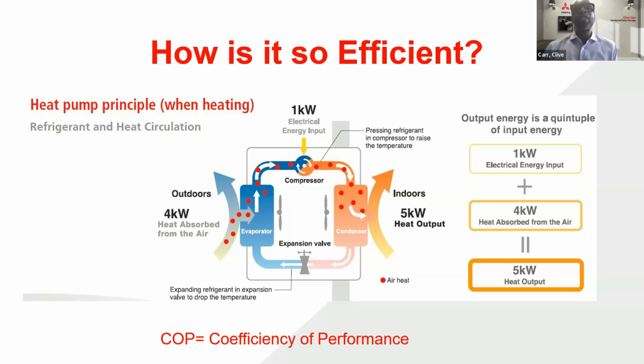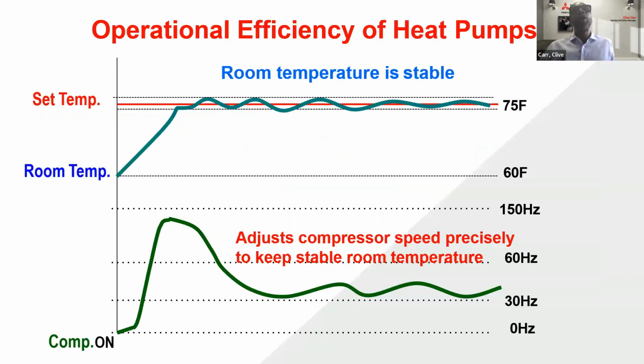The downside to this, which is becoming less and less of an impact on the technology, is that as the outside temperature gets colder, the efficiency and the heating output decrease. But the good news is that the majority of our days, hours and minutes during the winter period are spent at milder temperatures. Therefore, the heat pump delivers 100% of what is required to heat the space for most of the time. Our design temperatures only occur for 1% of the heating season.